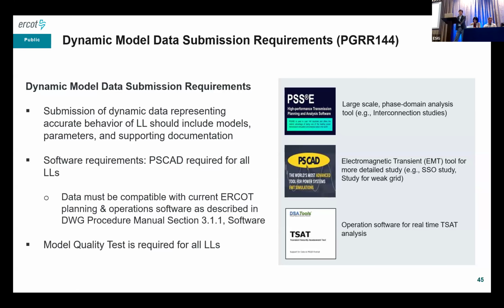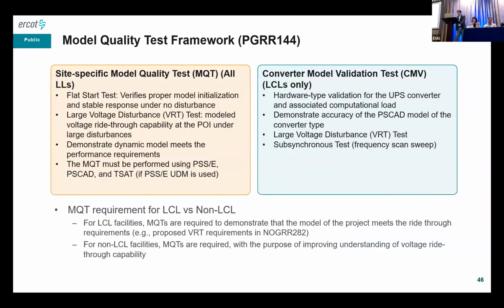For example, you can make sure that your PSSE model is in good shape by comparing the response of the PSSE model against the response from the PSCAD model. And so that's one of the important steps in the model quality test. So, MQT framework. We have created a separate section in the Planning Guide, Section 6, to describe the model quality test. It is very similar to the model quality test for IBR, but it's a much more simplified version.